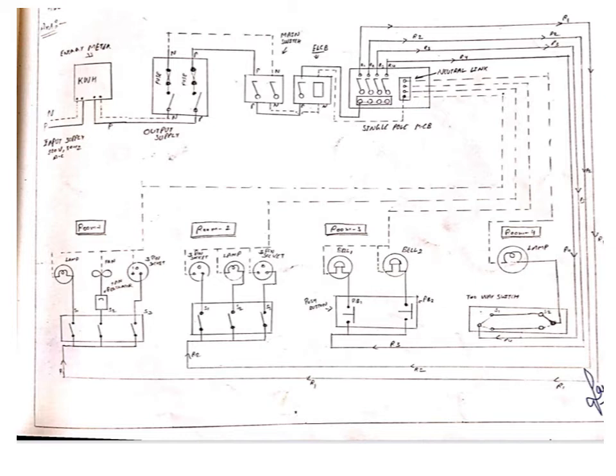and one lamp. Again, in the third sub circuit, we have to connect two bells. So two bells are connected by push buttons from the bus bar. Third, we have connected two push buttons to the phase wire, and then from this push button the bells are connected, and then neutral from the neutral link has been given to these two bells. Then the fourth sub circuit is the lamp, which is connected by two-way switches, that is the staircase.